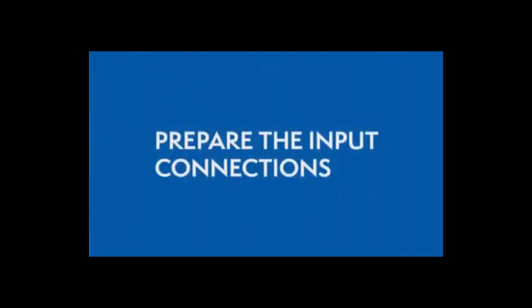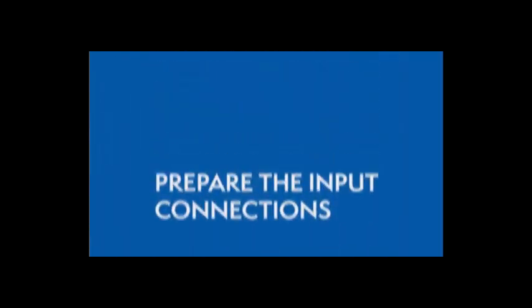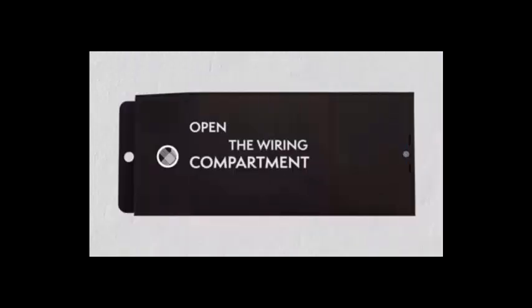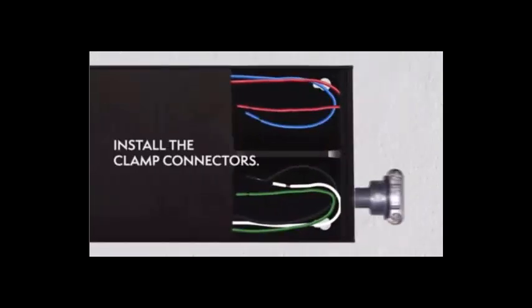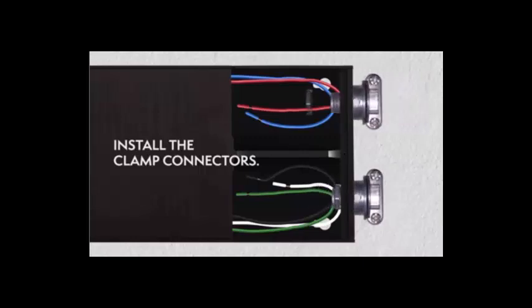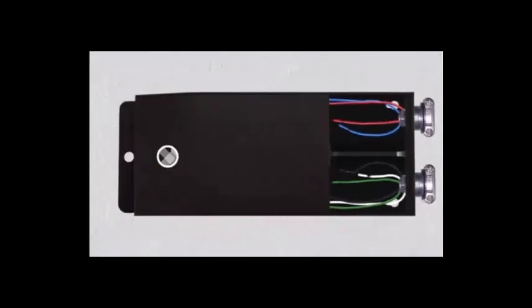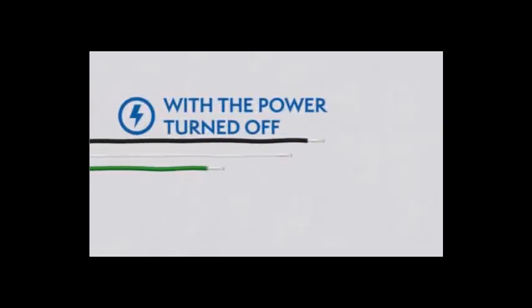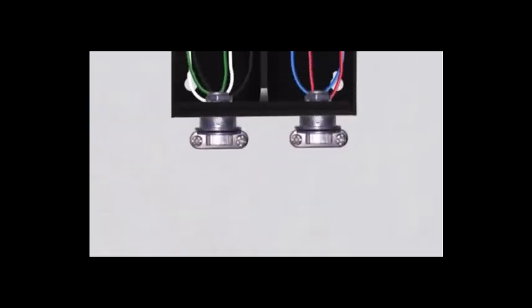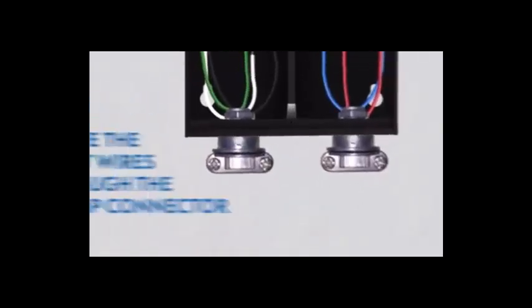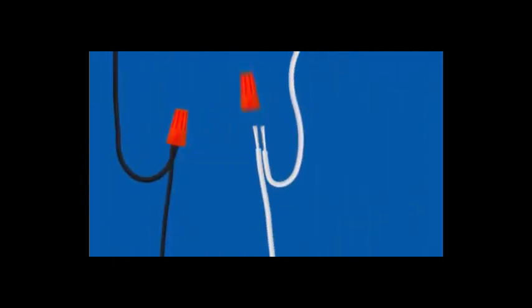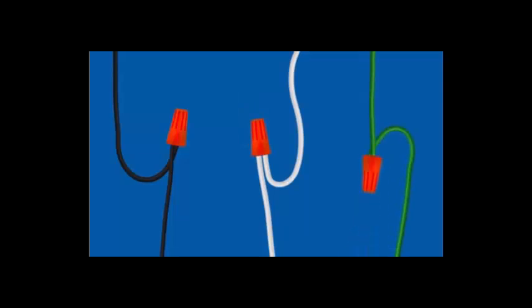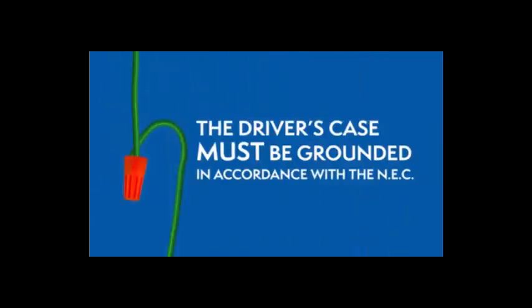Preparing the input connections. Open the driver's wiring compartment and install the clamp connectors. While the power is still off, route the input wires through the clamp connector. Then connect the wires using the UL listed wire nuts. The driver's case must be grounded in accordance with the National Electric Code.